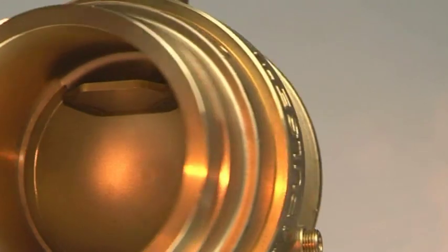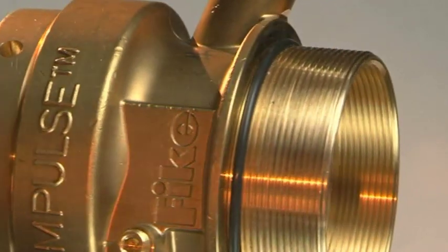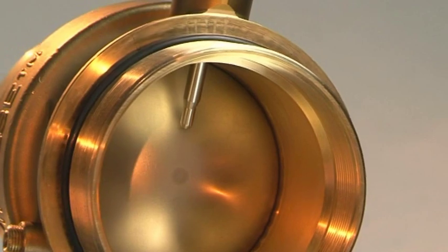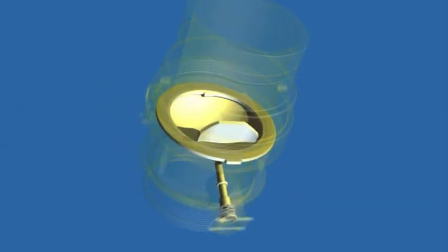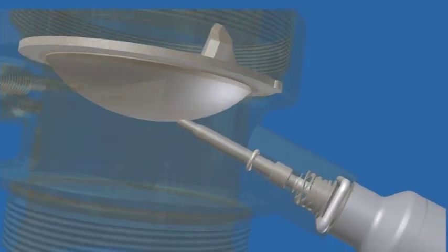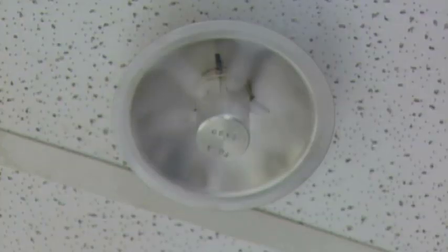The Impulse valve features FIKE's unique patented reverse-acting Axius rupture disc. The Axius surpasses all other rupture discs in its class. Within its unique operation, the disc creates a leak-tight seal until the firing pin impacts the disc. The valve is instantly fully opened, allowing the discharged gas to flow unimpeded into the protected area, all within 10 seconds.